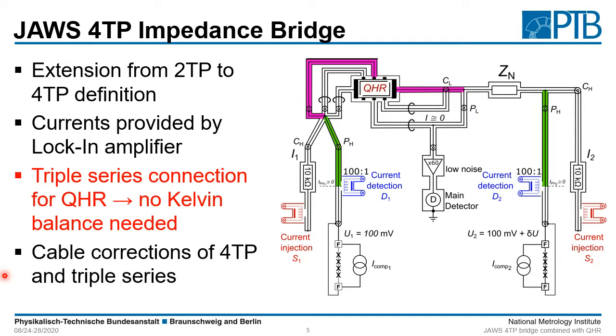Of course we have cable corrections also for this type of connection. The green marked corrections are the four terminal pair definition corrections, and the magenta lines are the cable corrections for the triple series connection.